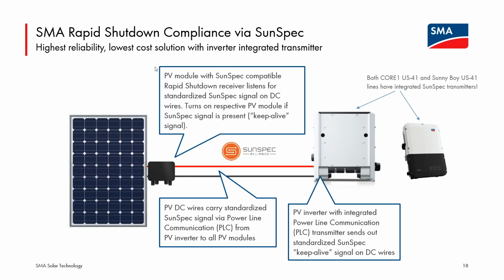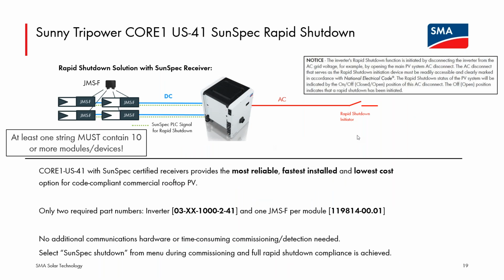All of the requirements for rapid shutdown can be met, along with some adequate labeling and decision of what the initiator for rapid shutdown should be. The way we have set up our inverters, once the transmitter board is turned on during commissioning, the array goes into operation. Once that happens, the inverter will take loss of AC power on its AC terminals as the signal to stop transmitting from the board out to the array. So that keep alive signal will stop.